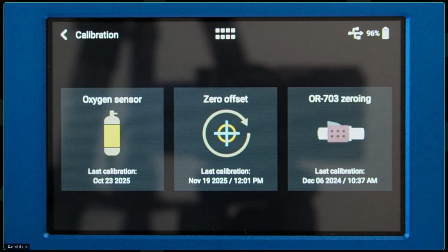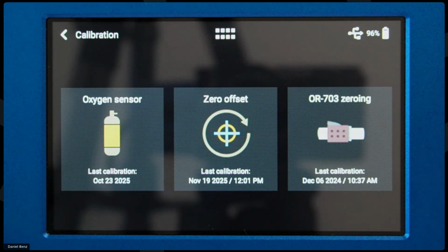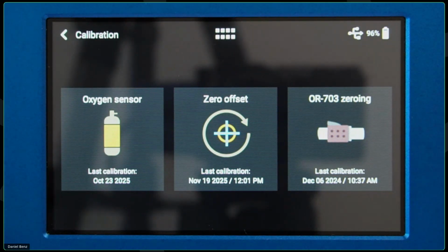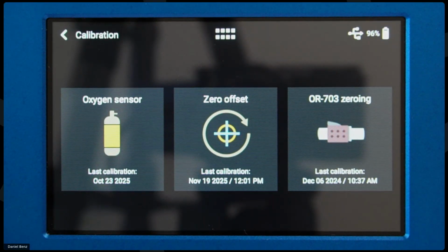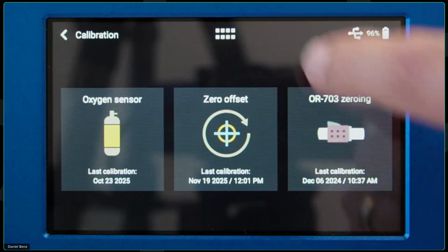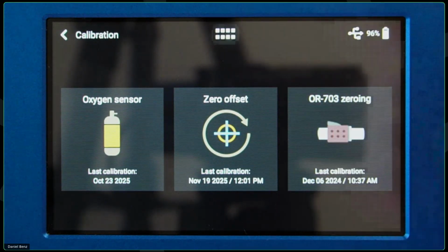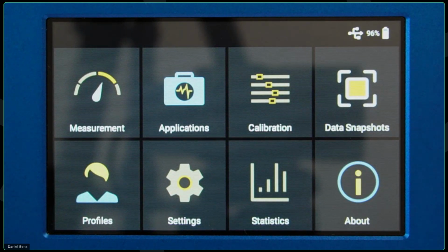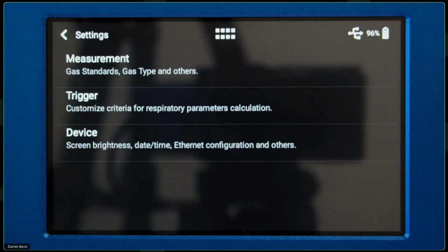Additionally, in this calibration screen, you can also perform a calibration of the built-in oxygen sensor and zero offset calibration of the OR703 multi-gas analyzer if one is connected. Then let's go back to the main menu with this button up here with the 8 tiles. You can get back and let's do some settings. Usually when you test a ventilator or another medical device, you want to make sure that your settings are correct. So of course the settings are in the settings screen.